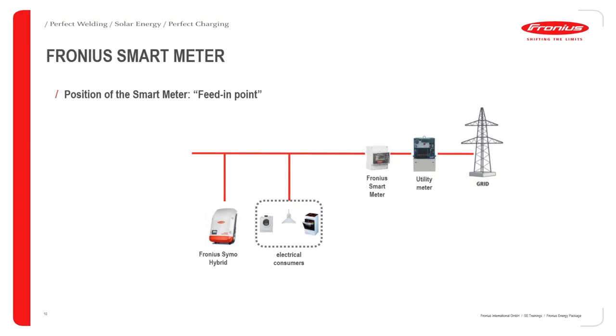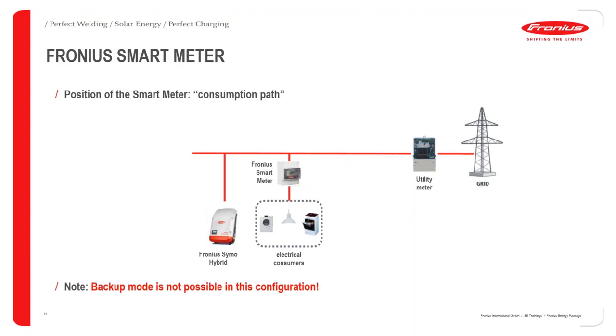So the Fronius smart meter can be installed in 2 different spots here. Some of you may have already used the smart meter a fair bit. When you select the function on there, it talks about feed-in point or consumption path. When we're talking about the feed-in point, which is pretty much all systems here in Australia, the loads and the inverter are on the same side of the Fronius meter. So whatever the smart meter is reading, the value of the inverter needs to be taken away from that.